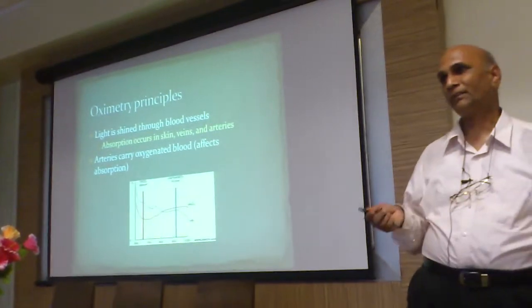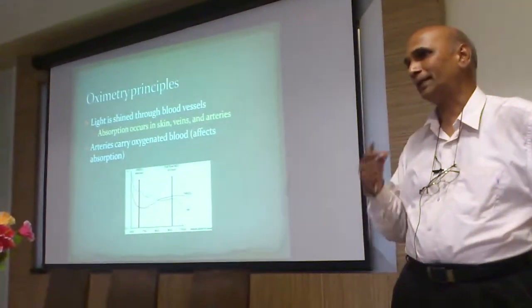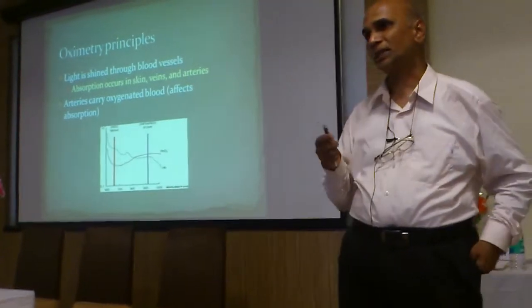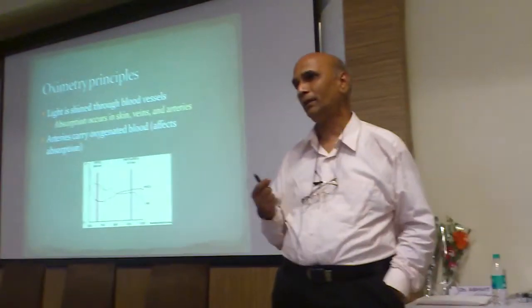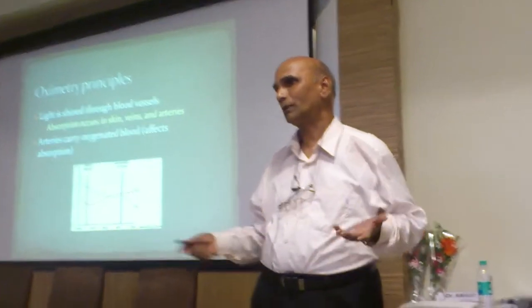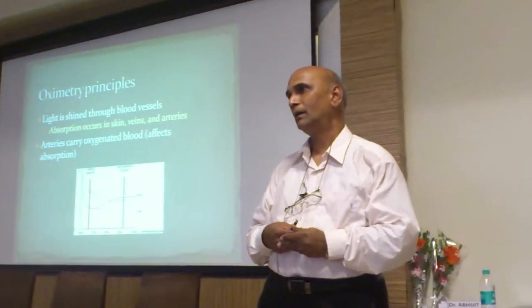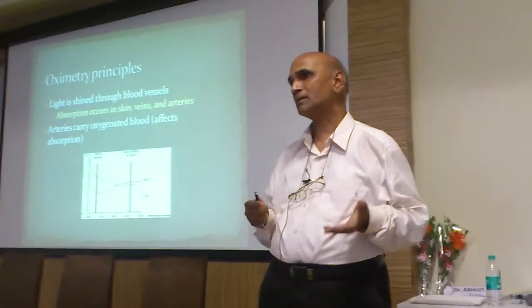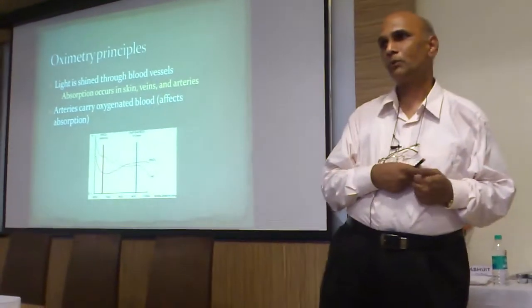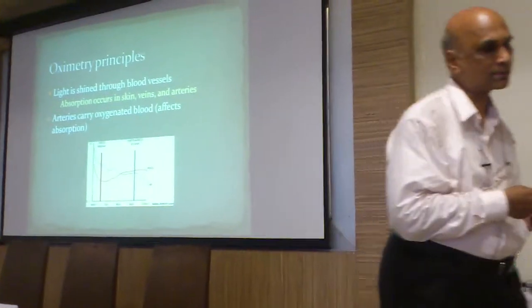There are two types: the reflective type and the transmission type. Particularly at the earlobe where there is no bone mass, we use a transmission type — that's the most sensitive part of the body. Other options are the fingertip or the toe of an infant. The forehead uses a reflective type of mechanism. So there are two types of oximeters: transmission type and reflective type.